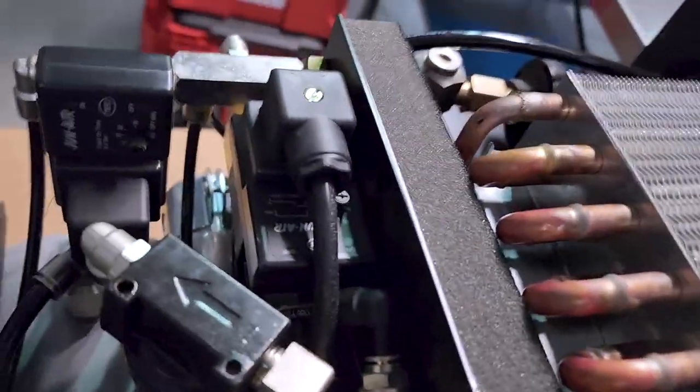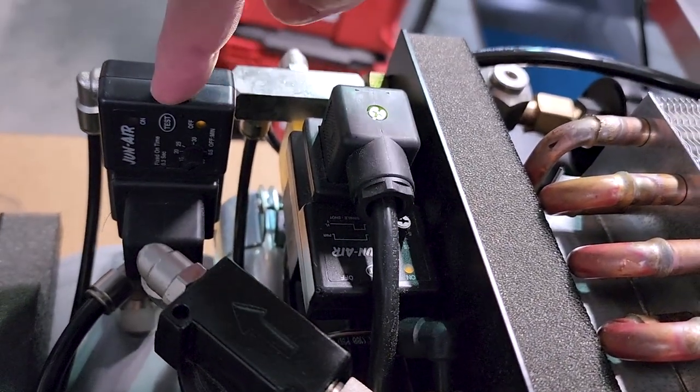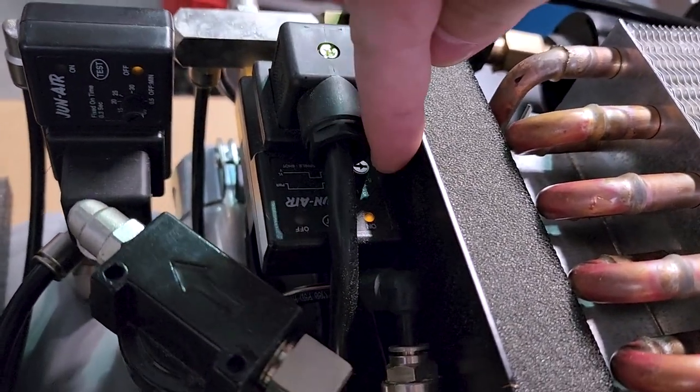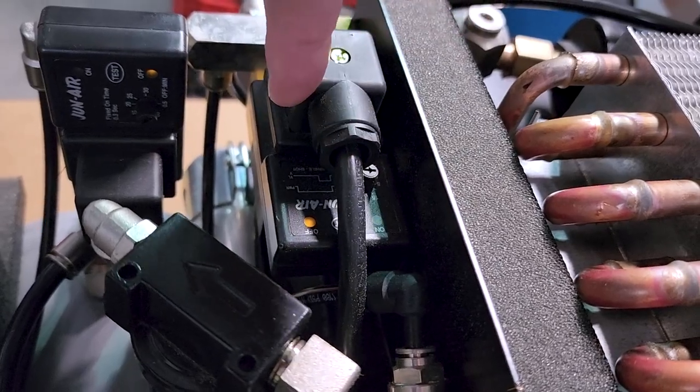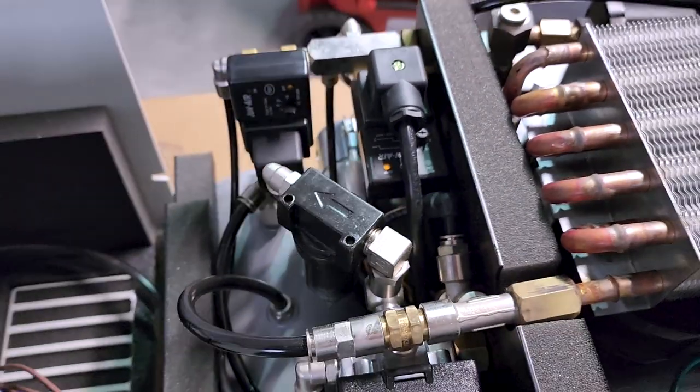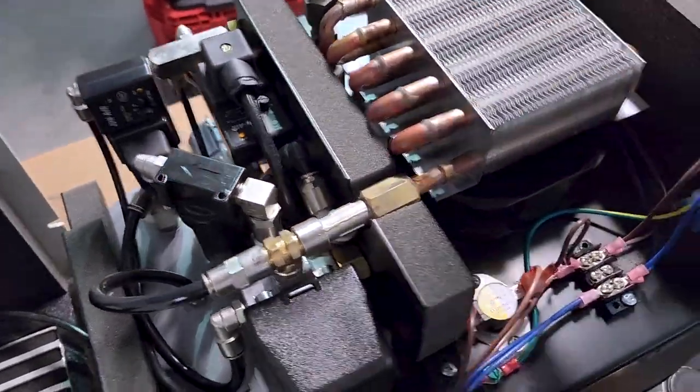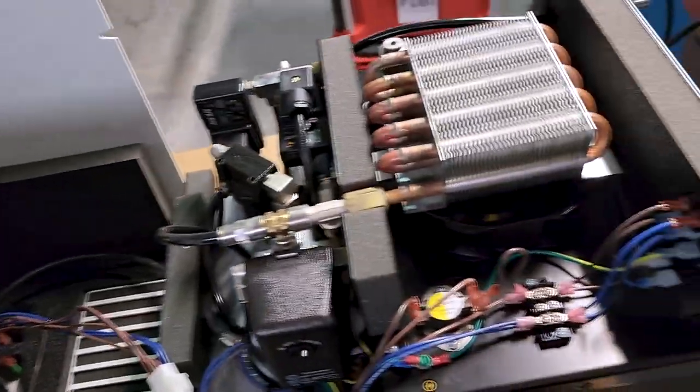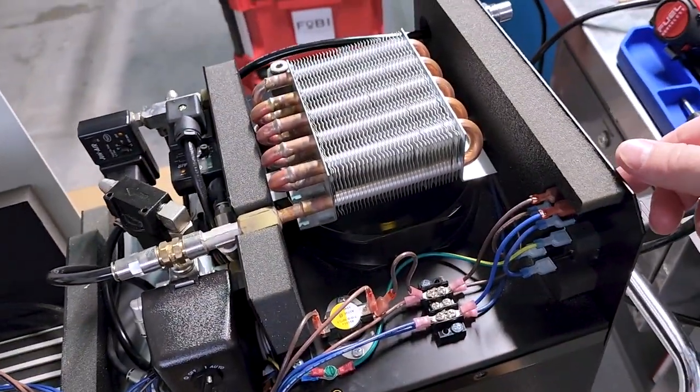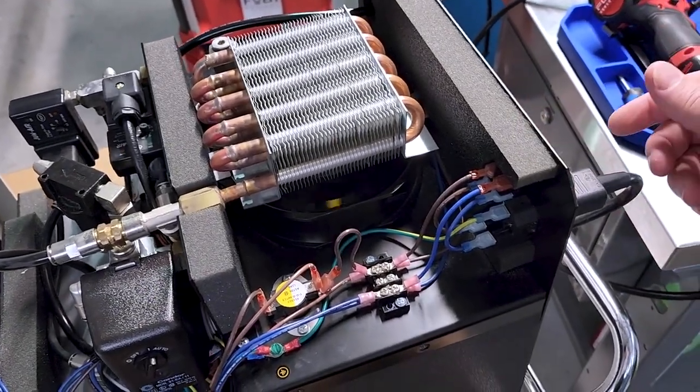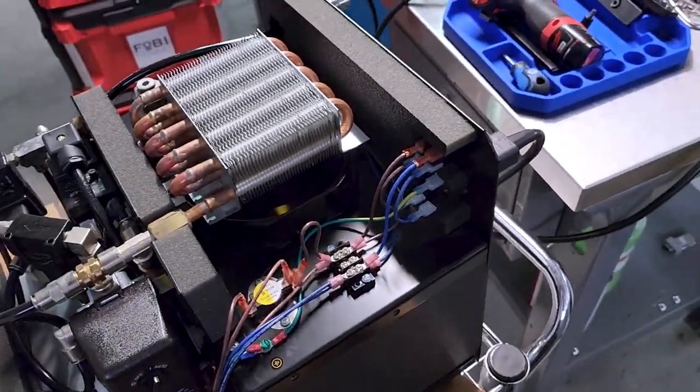Let's go ahead and vent it. It's a small reservoir. So luckily it builds pressure and it removes pressure quickly. There we go. All right. So I'm going to open it up so you guys can take a look at these guys right here and you can see how they function when it's running the cycle. They only last about five seconds and then they switch their state. Here we go. You can see it's in the off condition right here. And then you see this one here is in the on condition and it just switched. There you go. So that's it purging. Even with the cover off, it's super quiet. There's a lot of noise damping. The company, Junair, took a lot of extra conditions to make sure it's as quiet as possible. So that is a normal system.